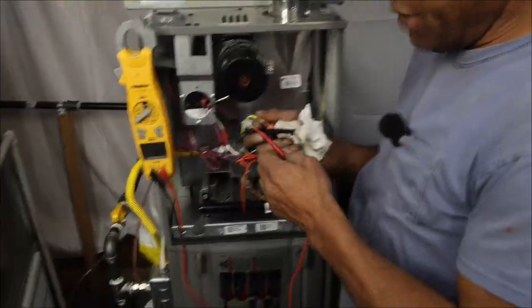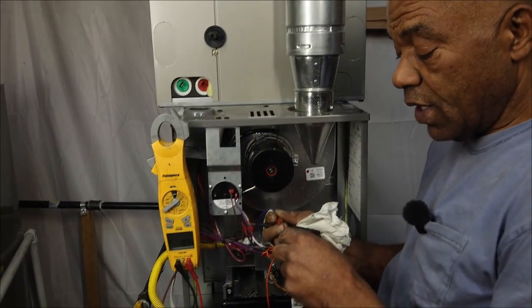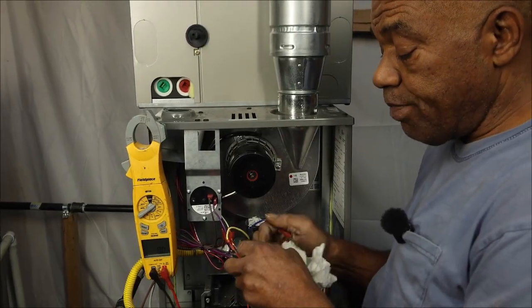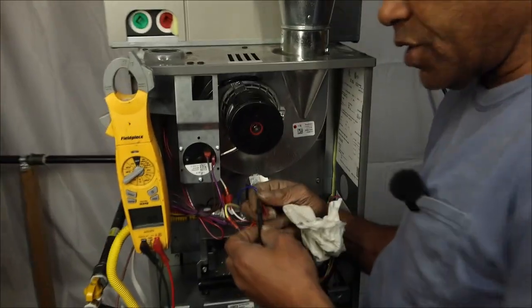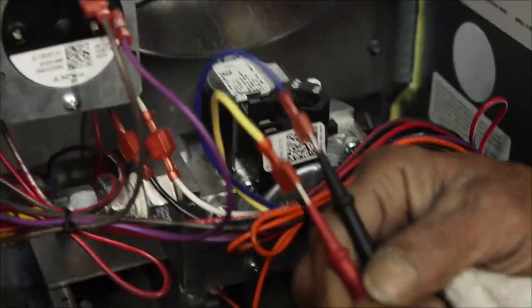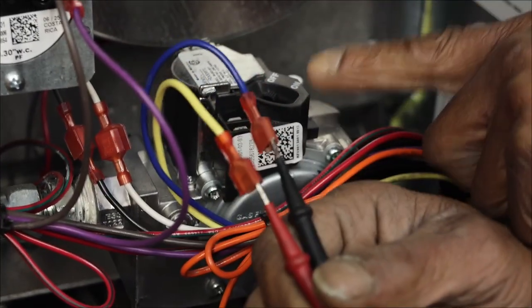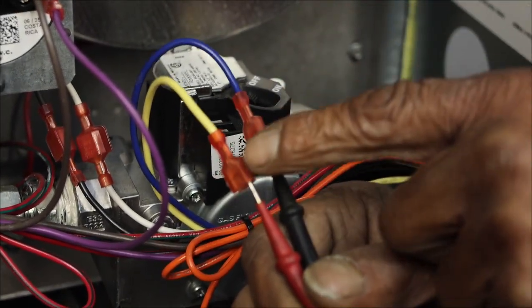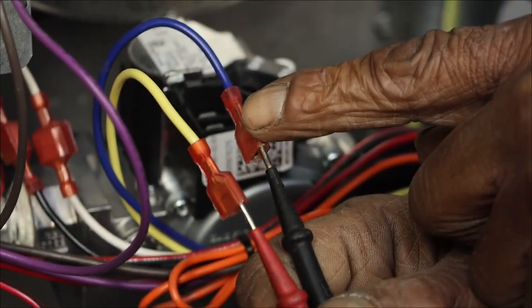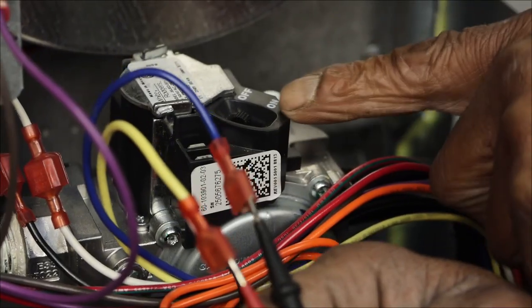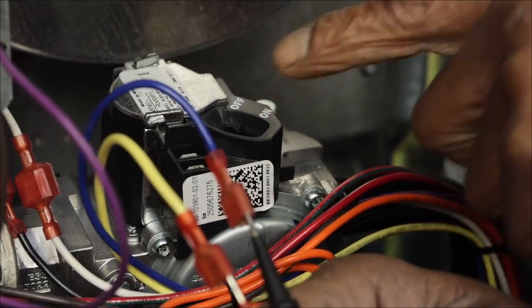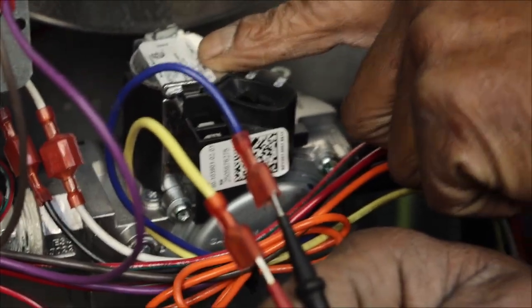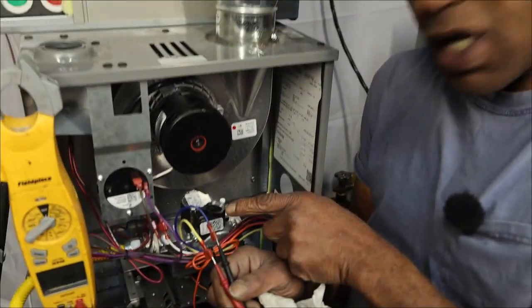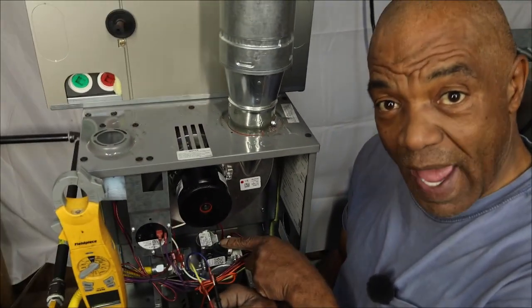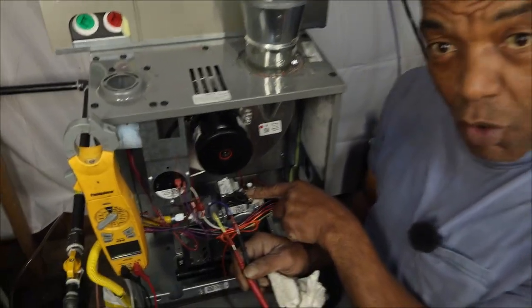okay? Then I would take my amp probe and I'd run the red into one side and I'd run the black into the other side because I'm trying to verify, does my gas valve work? This is not power in and power out. The gas valve is a device. It has a 24 volt coil inside of it, and it takes 24 volts in order for that gas valve to activate. So I'm going to turn the gas valve back on, okay?